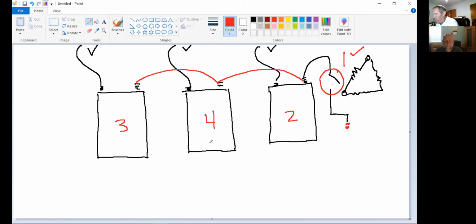So I've negated ferroresonance and voltage spikes. It's okay to open that bank up without closing in that ground switch, but when you energize it, you better make sure you close that switch in first. We did it both directions, on the open and the close of these three transformers. Like you say, there's different company policies for different companies.